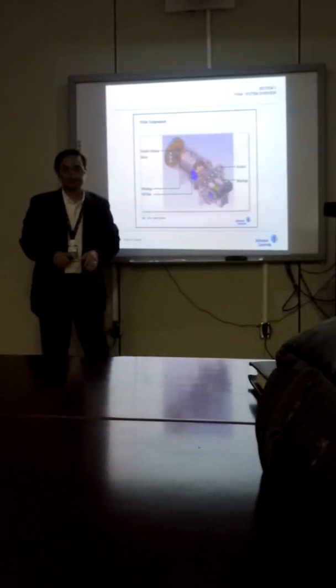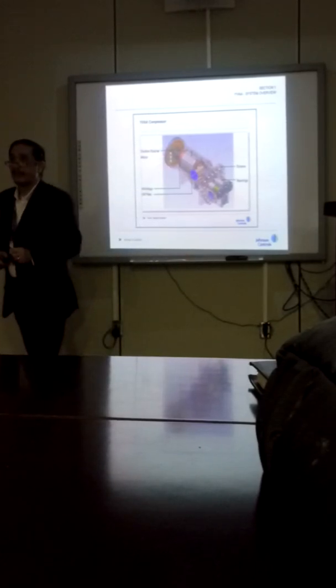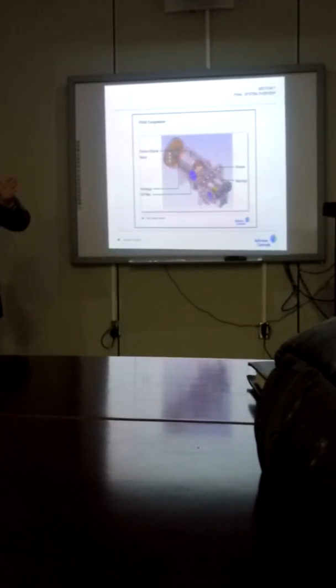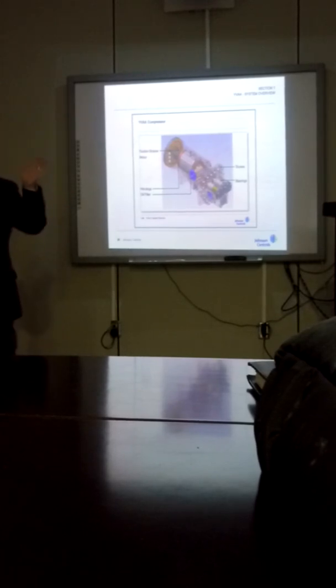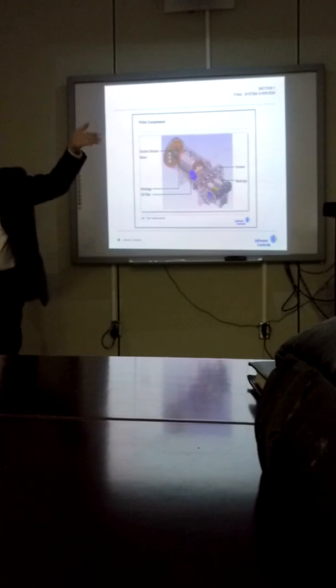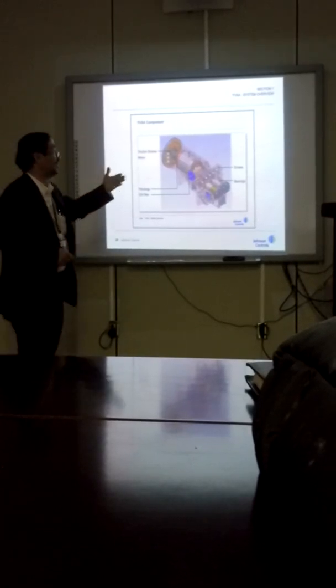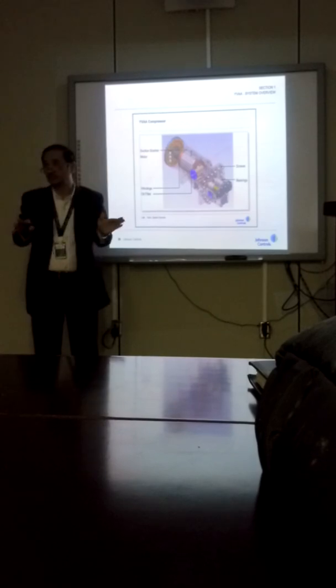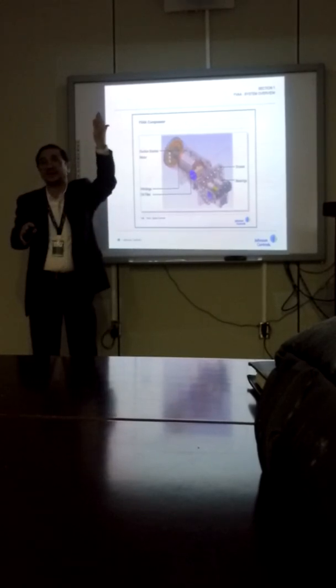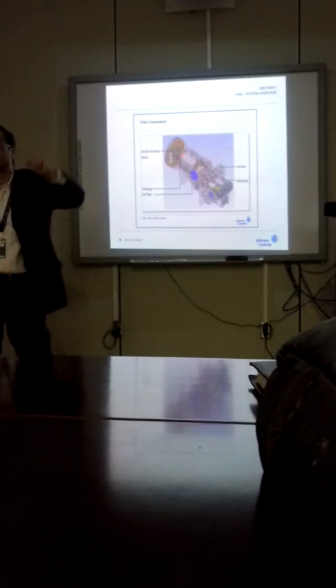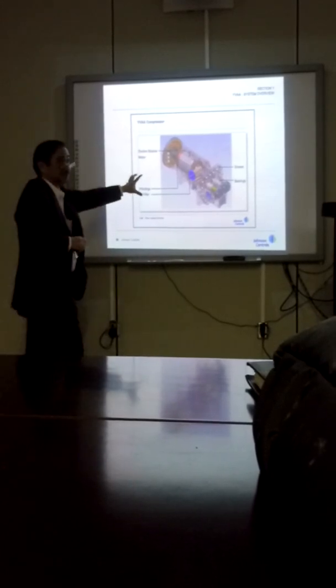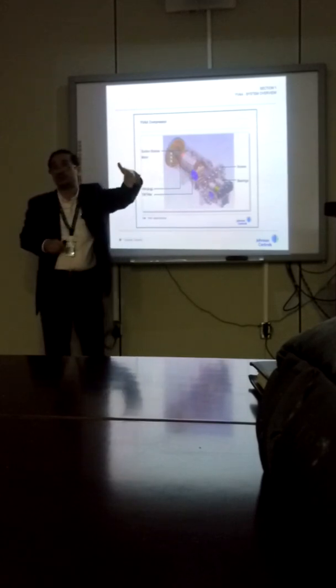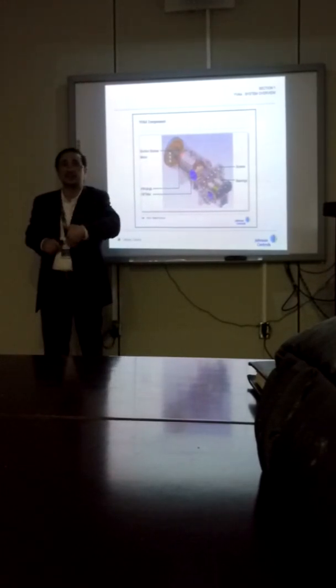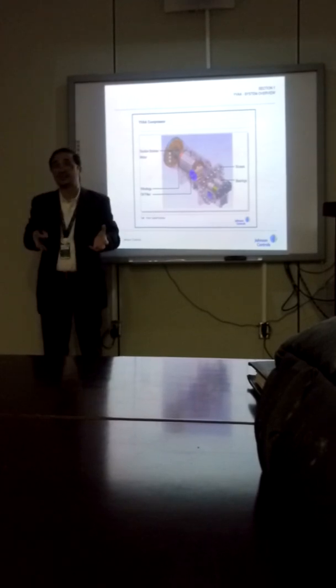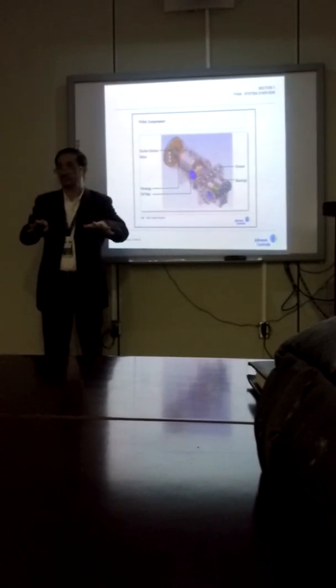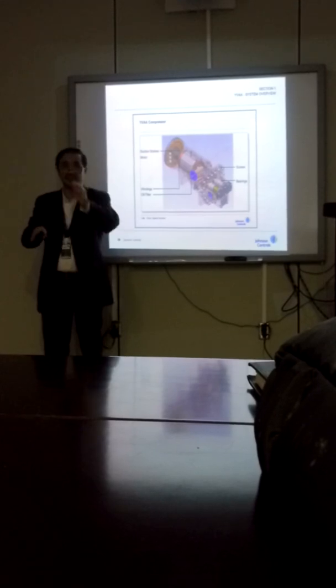It shows in the display, right? It shows an alarm in the display itself, showing that it's reaching this much. But before it reaches there, it will unload the system before it goes to high discharge, high temperature or high current, because we don't want the motor to heat up. The VSD monitors the temperature, pressure, saturation, superheat, subcooling, everything. Then it analyzes, hey, there's something wrong, I need to unload while maintaining the temperature.